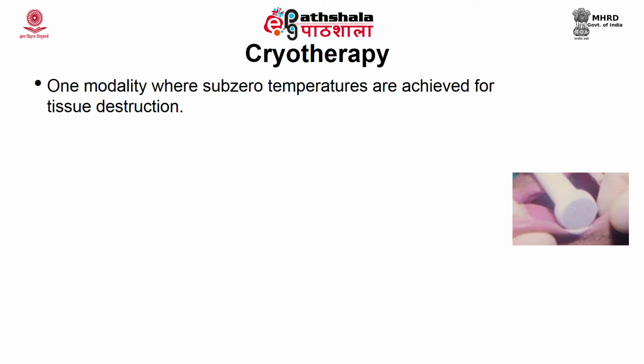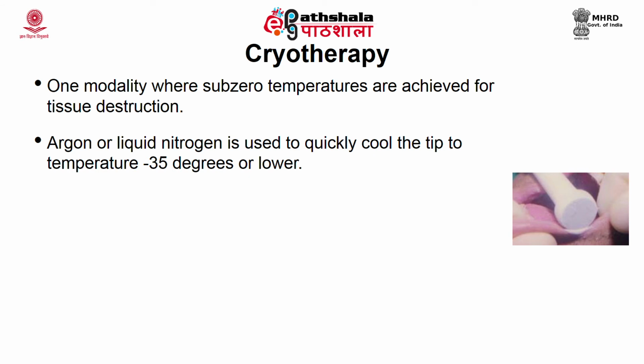Now what happens is, in the tip of the probe, liquid nitrogen or sometimes cooled argon gas flows very rapidly, which quickly drops the temperature of the probe to minus 30 degrees or even lower.